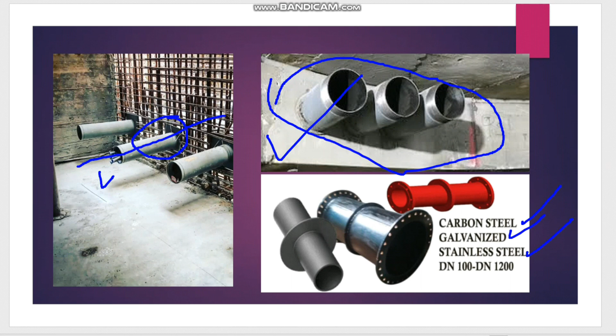Normally this puddle flange comes in different materials like carbon steel, galvanized steel, stainless steel, etc. This material is mostly based on the main pipeline material. For chilled water or district cooling systems, normally we use carbon steel ASTM A53 - I explained the grade and schedule in the last video. So mostly the puddle flange material will match the same carbon steel material fixed in the wall.